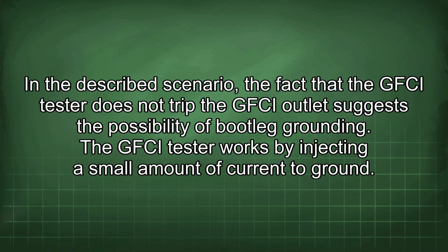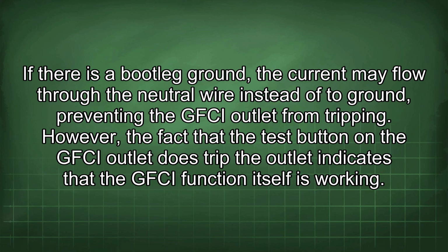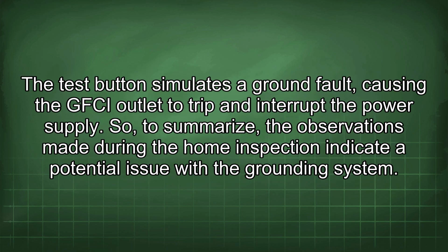In the described scenario, the fact that the GFCI tester does not trip the GFCI outlet suggests the possibility of bootleg grounding. The GFCI tester works by injecting a small amount of current to ground. If there is a bootleg ground, the current may flow through the neutral wire instead of to ground, preventing the GFCI outlet from tripping. However, the fact that the test button on the GFCI outlet does trip the outlet indicates that the GFCI function itself is working. The test button simulates a ground fault, causing the GFCI outlet to trip and interrupt the power supply.